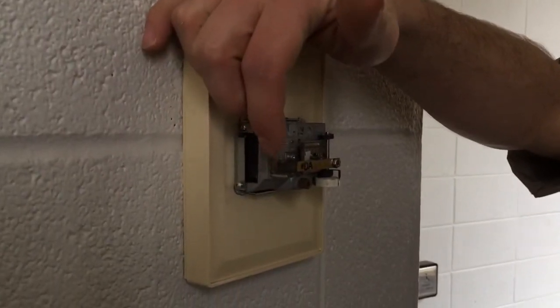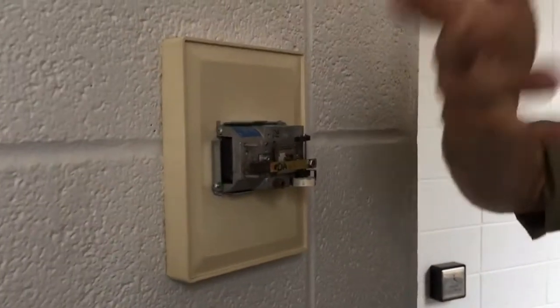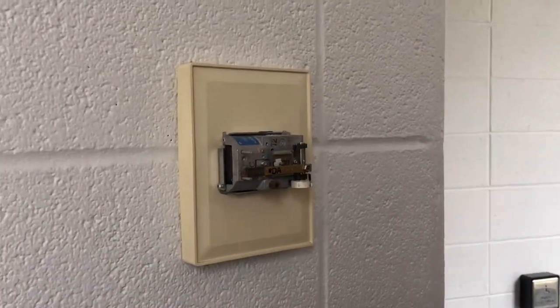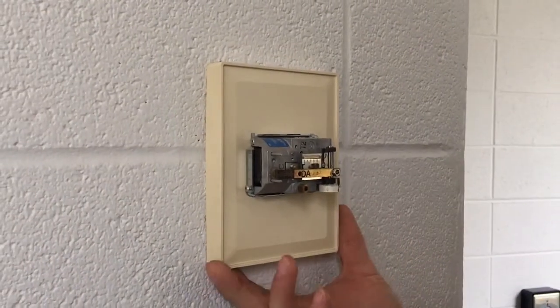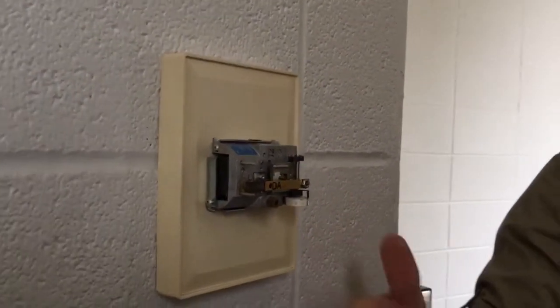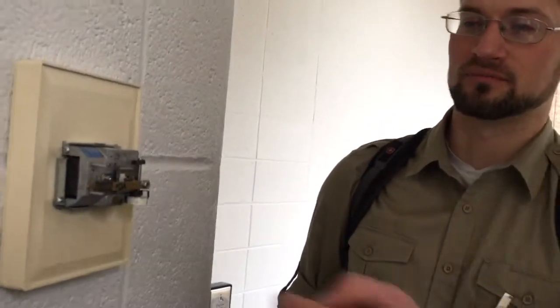The first thing I like to check on thermostats is how clean they are. If you get a lot of dust buildup here on the exhaust port, it won't seal all the way and you'll vent pressure. If you vent pressure, typically on these you go to freeze protection, which is full heating. So it's important that these be able to seal all the way.